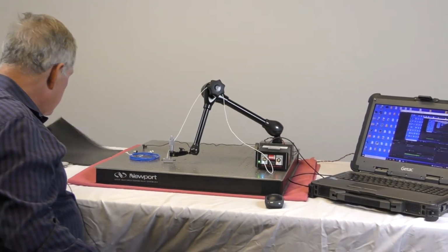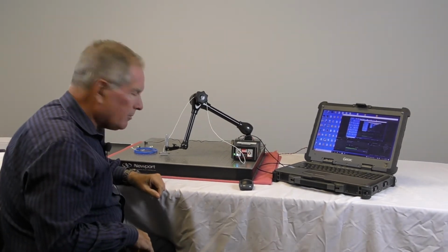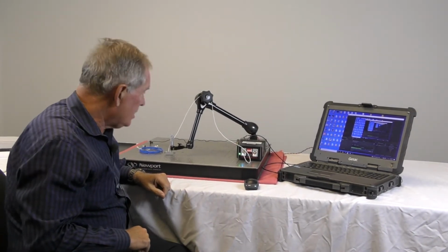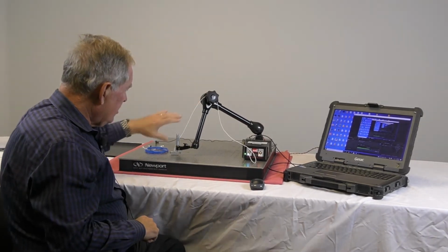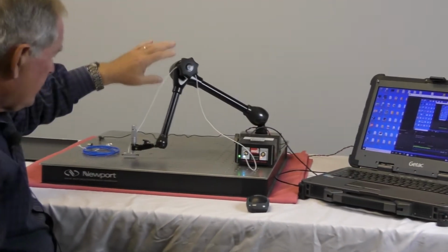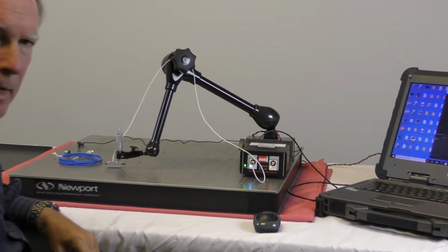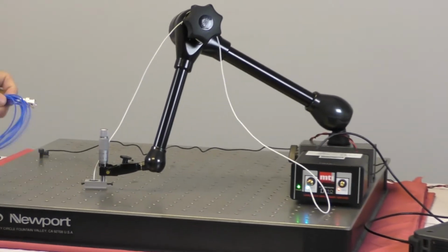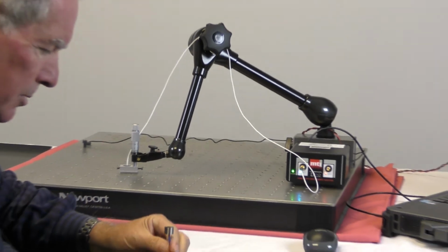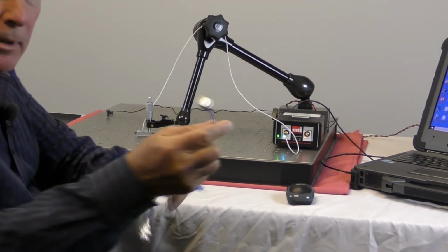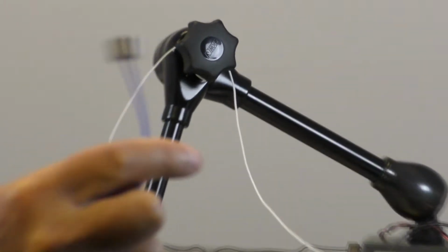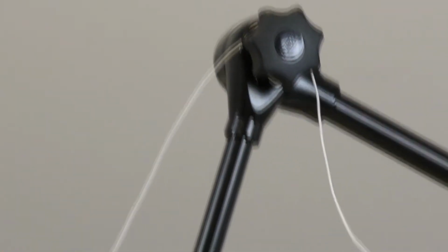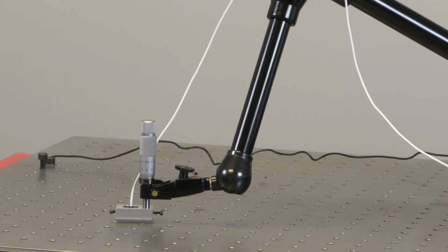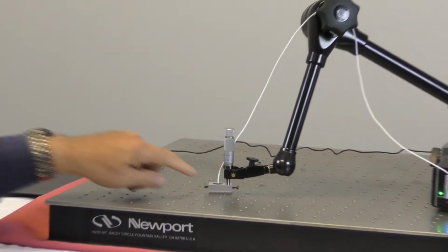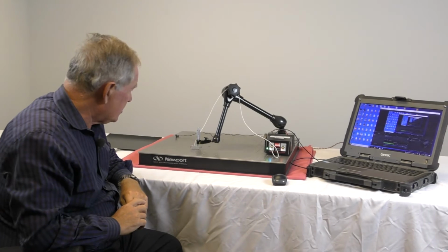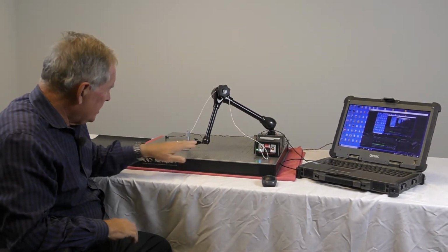So the first thing I'd like to talk about is what equipment we need to make these measurements. We're going to need something to hold the probe, and here we have a fixture. This is an adjustable arm that's holding a probe, and capacitance probes are what we're using to make this measurement. This is an example of the probe, held by the fixture right here, and we have a little micrometer that's used to adjust the height, and we'll talk about why we want to do that in a minute. The other important thing is we need a ground plate.